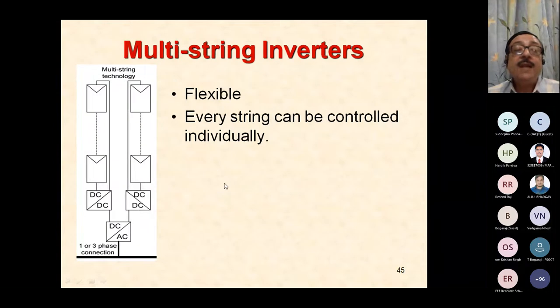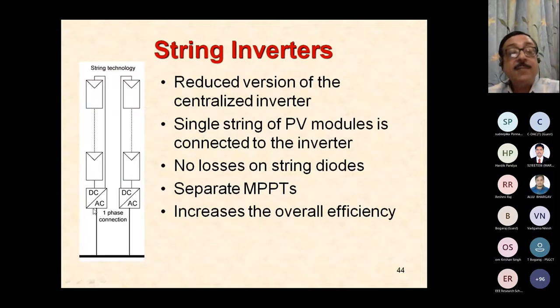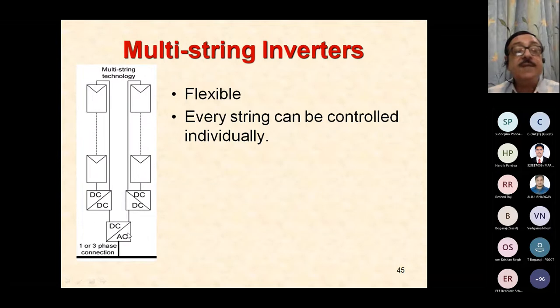You can have multi-string inverters, where in the earlier case, we had an inverter per string. Here you do have a single inverter, but every string has its own MPPT operated DC to DC converter. So here you have a degree of flexibility involved. Every string can have its own DC to DC converter for its own MPPT operation. That gives you better operation even in partial shading. Suppose this string is partially shaded, its own MPPT will give its own global MPPT, and this one may not be shaded.